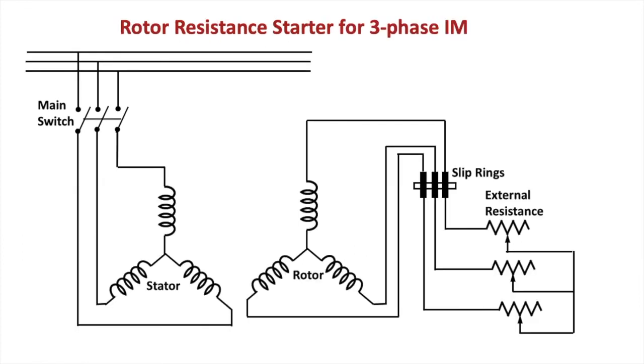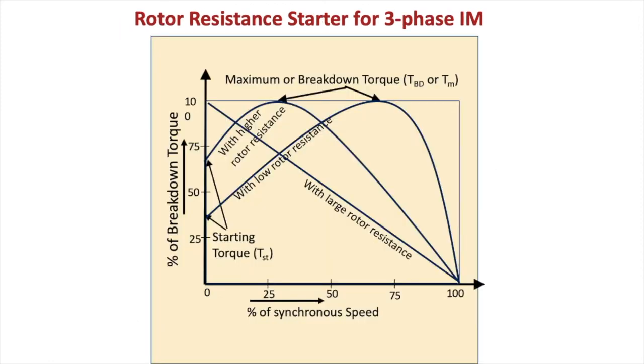Then we also have the rotor resistance starter, but it has its limitation that it can't be used on the squirrel cage induction motor. It can only be used on slip ring induction motors, where we can insert external resistance in the rotor circuit, and if the external resistance is added in the rotor circuit, we change the instant of the maximum torque occurring in the given motor. So we increase the rotor resistance, have the maximum torque at the start, and slowly as the motor picks up the speed, we cut out the external resistance and the motor starts running with no external resistance, completely short circuited at the slip ring terminal.